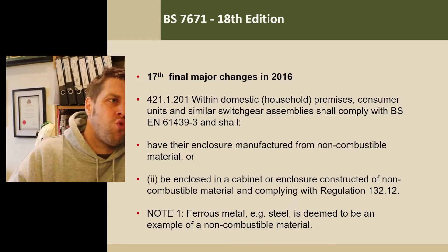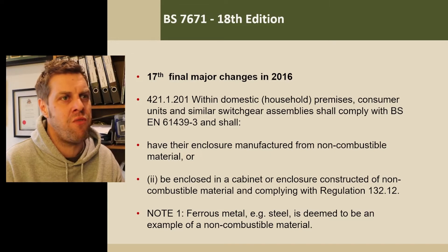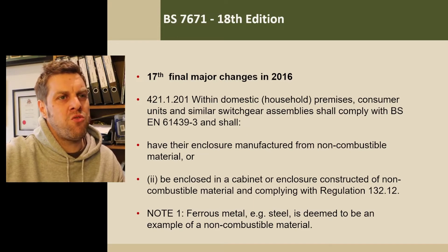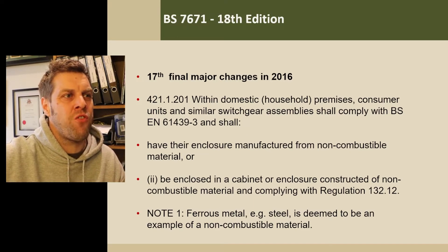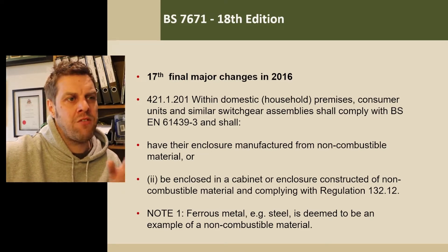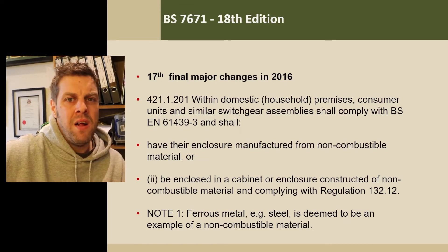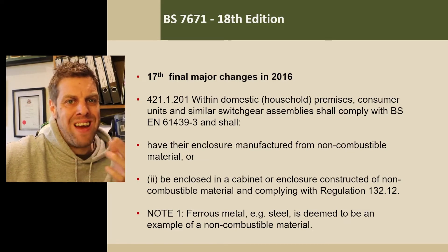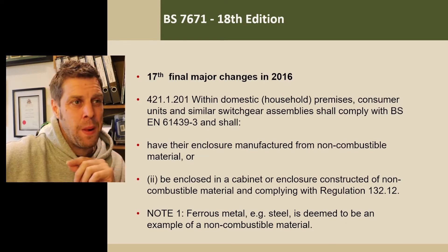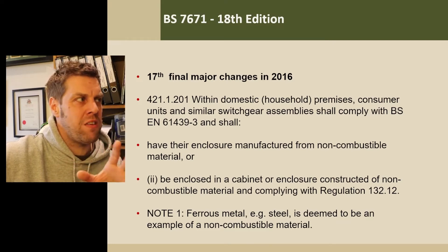Going back to the 17th edition, the final major changes in 2016 were that within domestic households, consumer units and similar switchgear should comply with BSEN 61439-3 and shall have their enclosures manufactured from non-combustible material, or be enclosed in a cabinet or enclosure constructed of non-combustible material and comply with regulation 132.12. People often say that all fuseboards in the domestic environment have to be metal — that is not true. The regs don't say that. Check it — you can use plastic fuseboards if they're made from non-combustible or self-extinguishing plastic.